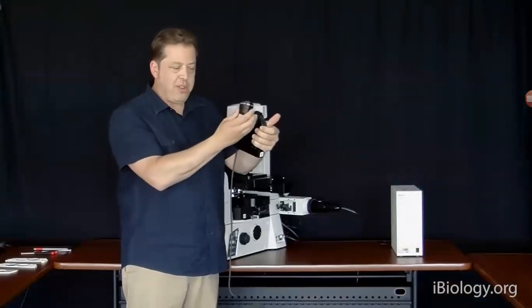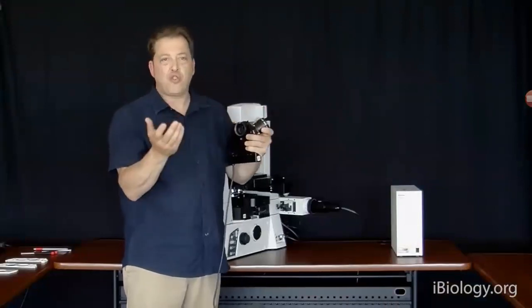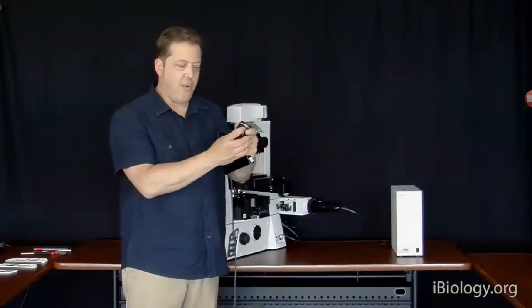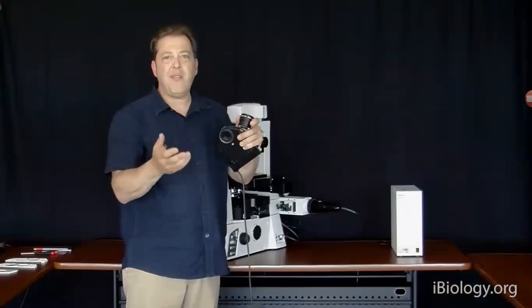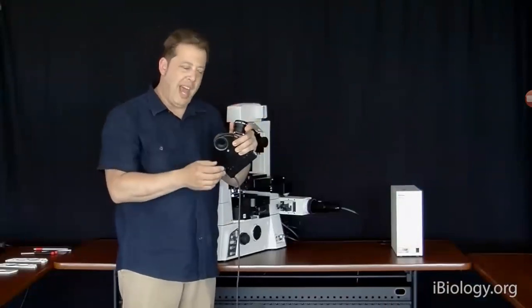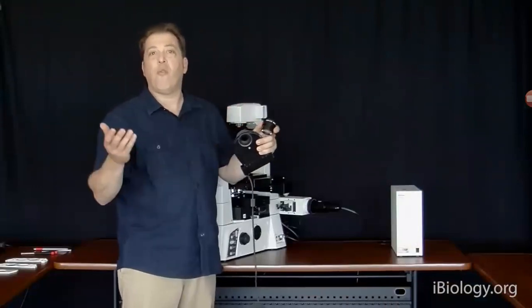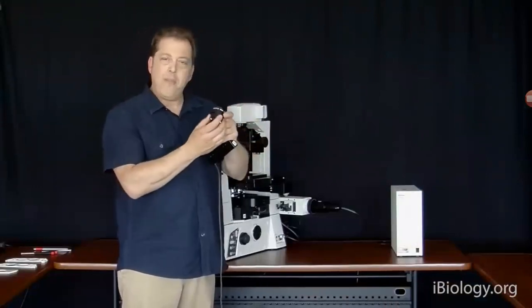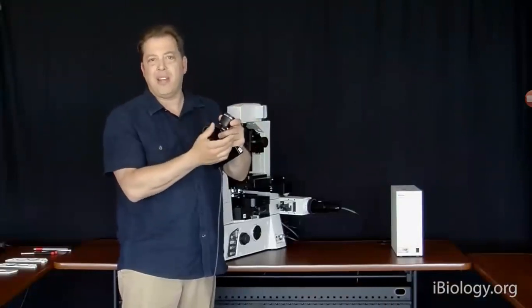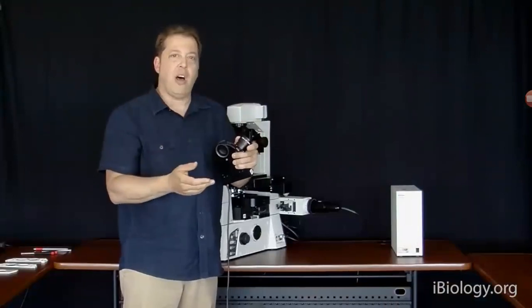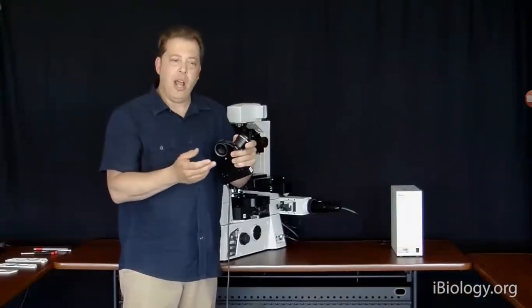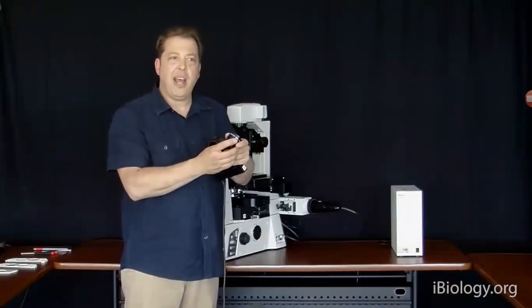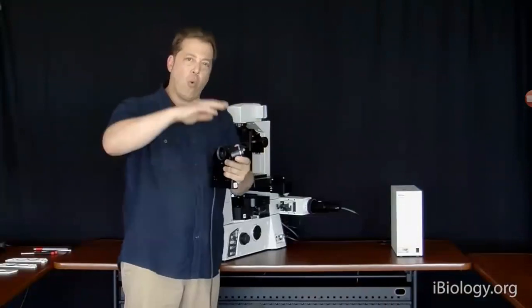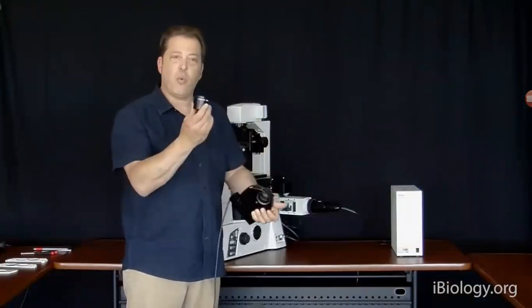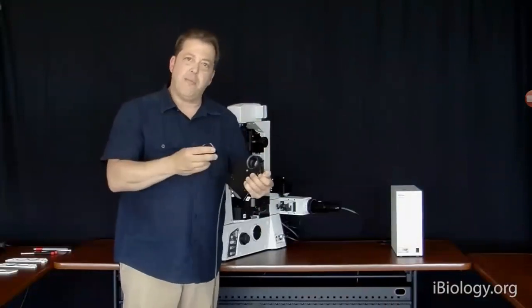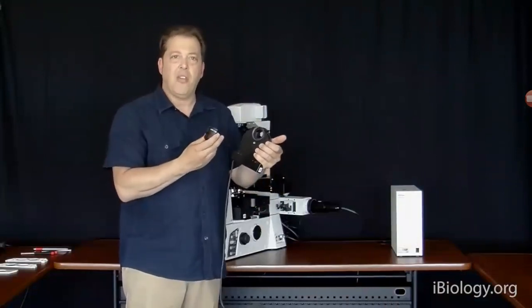And we can put multiple condenser lenses on this, always trading off working distance versus resolution. So if we have 0.52 numerical aperture, it's going to significantly limit the resolution in transmitted light that you can get with, for example, a 1.4 NA oil immersion lens. That's why we make several different compromises. We make condensing lenses that are high NA oil that actually have a numerical aperture up to about 1.4. We make a 0.85 dry, and basically all of these different options will trade off the working distance versus the resolution. This one gives you many inches of working distance, so you can manipulate the specimen, put large specimens on the microscope.